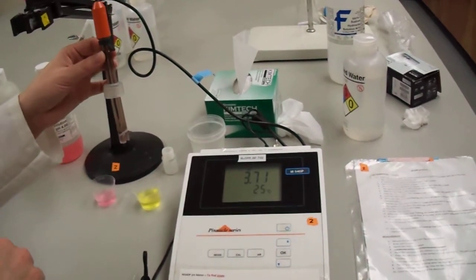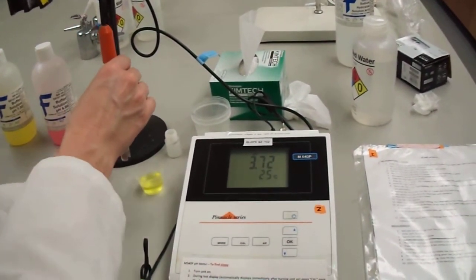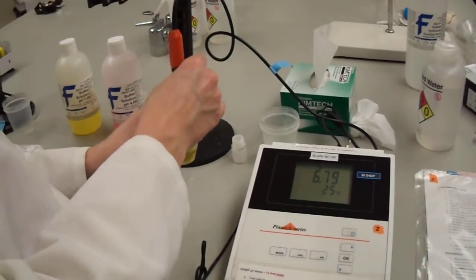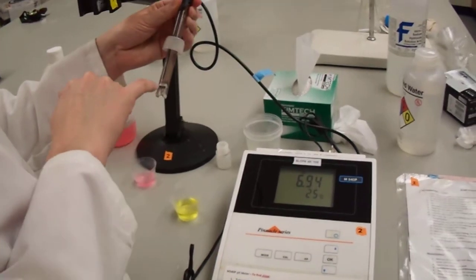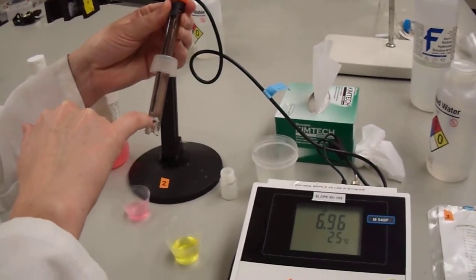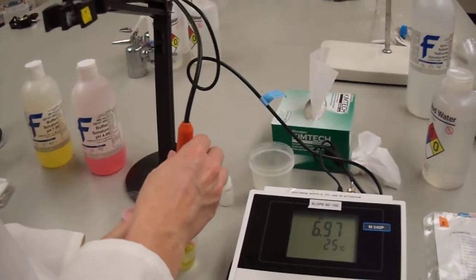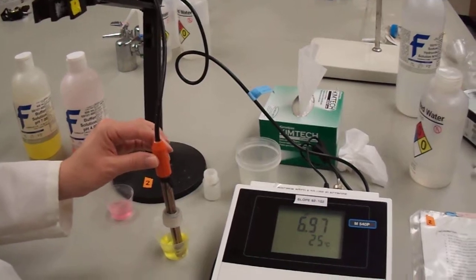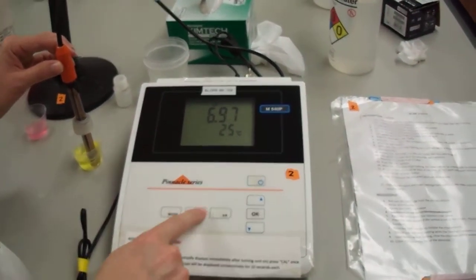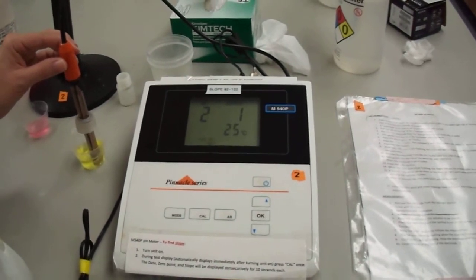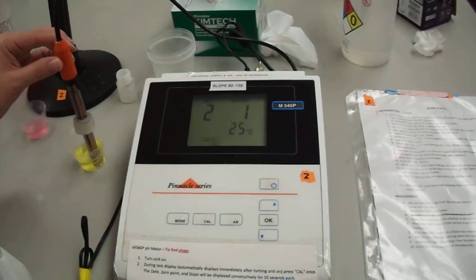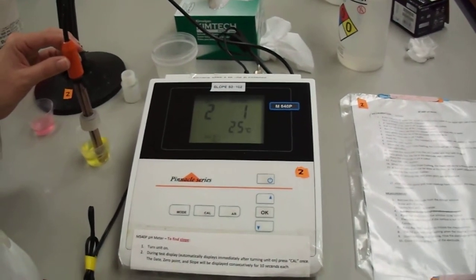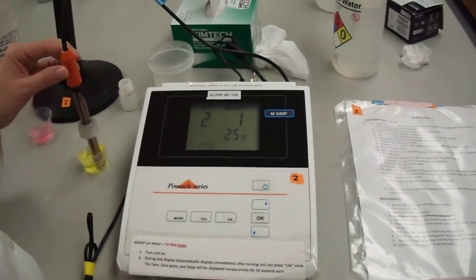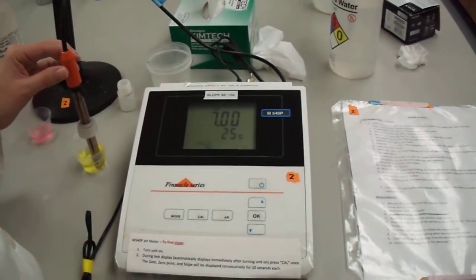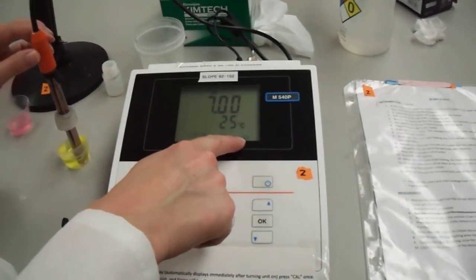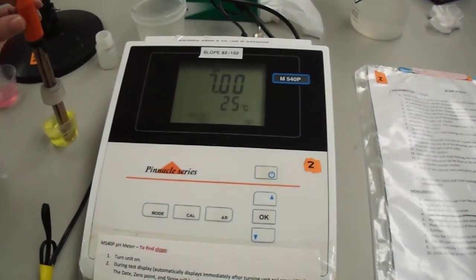Okay. So now you're going to place the electrode in the pH 7 buffer. Yellow was our pH 7, and you want to make sure that the probe is all the way down in there. If you submerge it about this high, that's probably a good place to make sure it's covered. So it is covered in there. Then you're going to press the calibration button, and the numbers 2 and 1 will appear on the screen. 1 signifies the first buffer. And then press OK. When the AR icon stops flashing, the meter will ask for the second buffer by displaying a 2, which signifies the second buffer.